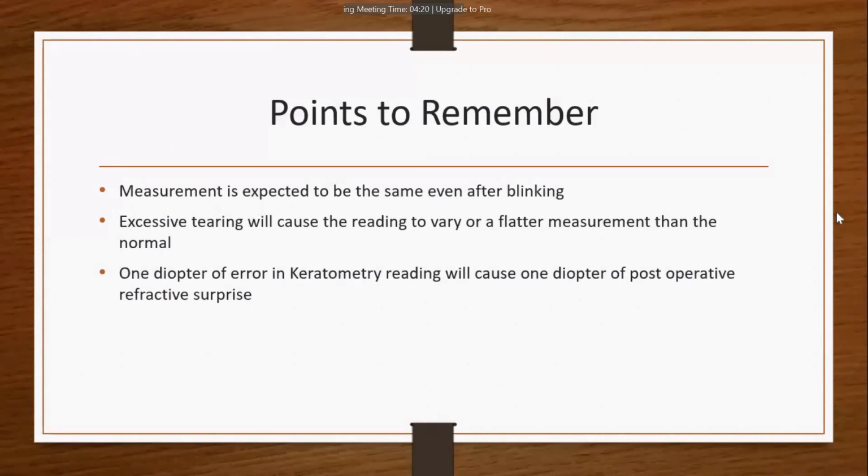It will not, if it is for each and every time, if the patient after blink, if the values are going to differ, then you want to repeat the keratometer values. And the patient who is having an excess tearing, which is nothing but epiphora, will have a variation in the reading. So in that case, you want to clean their eyes, and then you can go for a topography system for mapping their cornea.